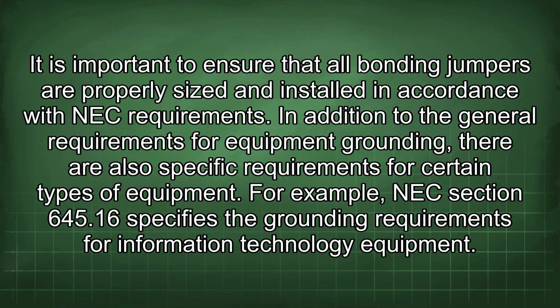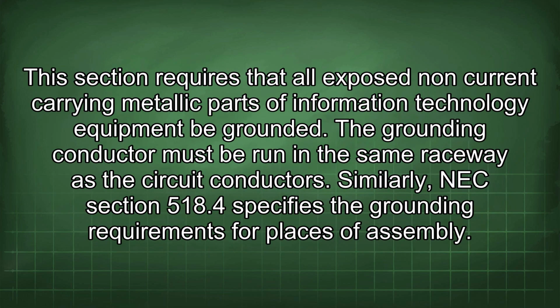In addition to the general requirements for equipment grounding, there are also specific requirements for certain types of equipment. For example, NEC Section 645.16 specifies the grounding requirements for information technology equipment. This section requires that all exposed non-current carrying metallic parts of information technology equipment be grounded. The grounding conductor must be run in the same raceway as the circuit conductors.